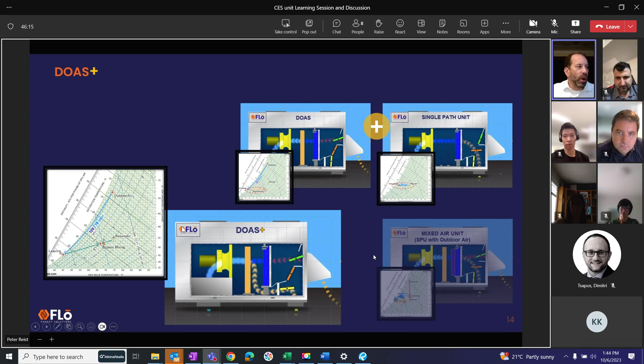Now, the obvious objection, and I'm always looking for objections, is, okay, but hold on, Peter, what happens if that return air needs some additional cooling itself, or some additional dehumidification or something of that sort, because I'm bypassing it? So our company, we never just leave it here. We take it even another step. So our product is actually considered a DOAS Plus with adaptive multipath technology. We have this other set of dampers that allows us at times to also bring up some of that return air and put it across the coil.